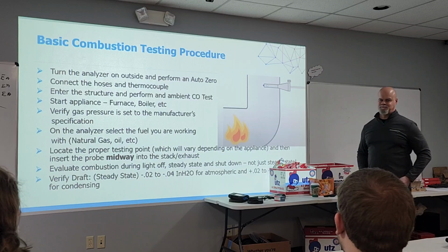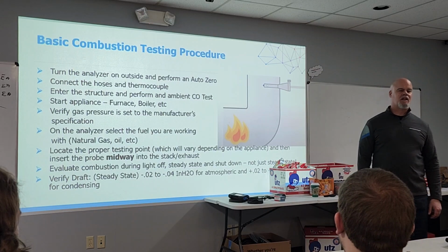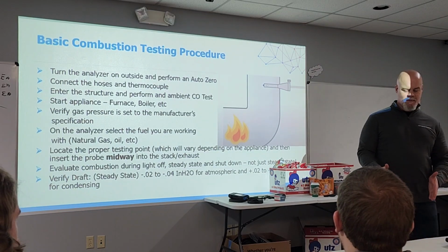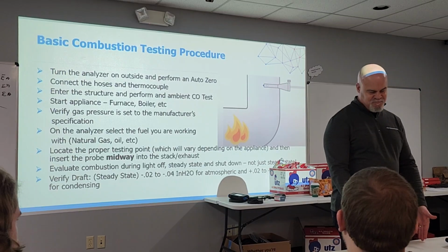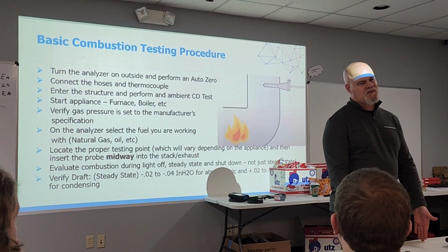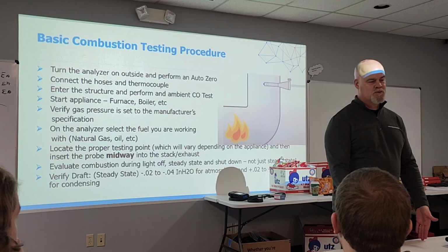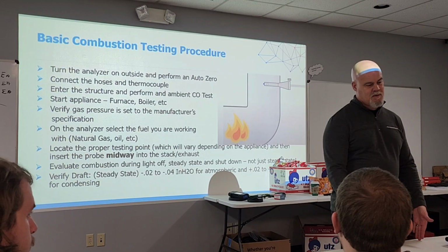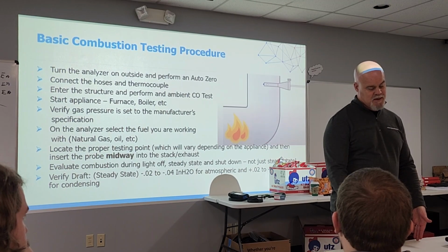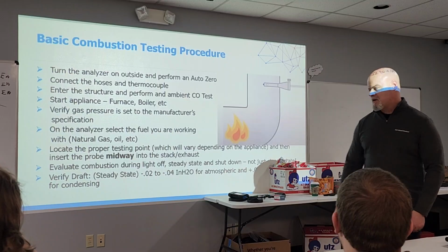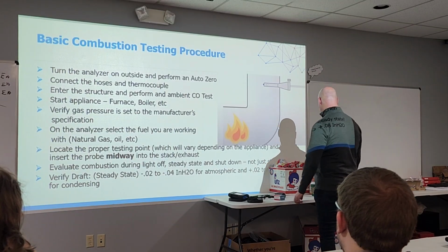I don't care about that. I want 0. I don't want tolerances. When we're talking about this, we're talking about controlling variables. I don't want you constantly working in a condition where there's 5 ppm. That's BS. Windows would be open, place would be evacuated, you would get to the heart of the matter and find out what's doing it. I want 0 ppm in the space that you're testing it, okay? So it's not up to debate.